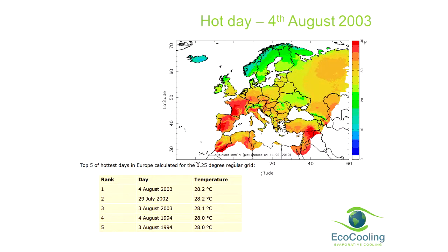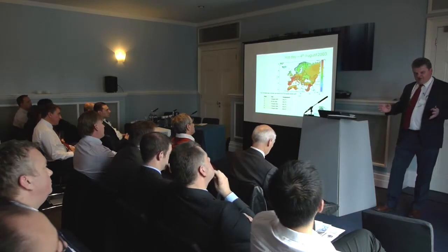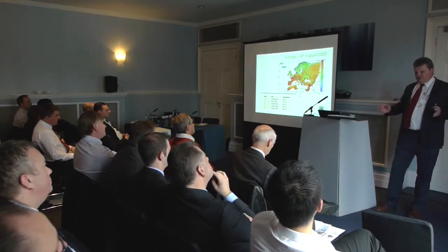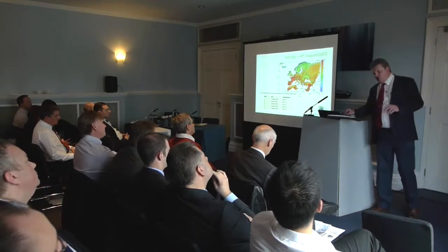We've then got these very, very hot days to deal with, record hot days. So we will look at these conditions. When you're designing a resilient data centre, your infrastructure should be capable of supporting not just the average conditions outside, it has to be capable of coping with the extreme temperatures. Now in London, we have had 37 degrees centigrade ambient. That actually manifests itself as temperatures of 40, 45 degrees centigrade around your condensers or dry chillers or whatever. So your equipment needs to be designed to accommodate that.